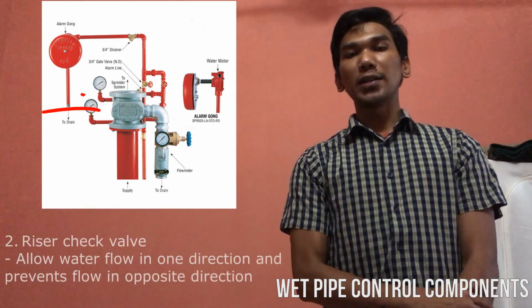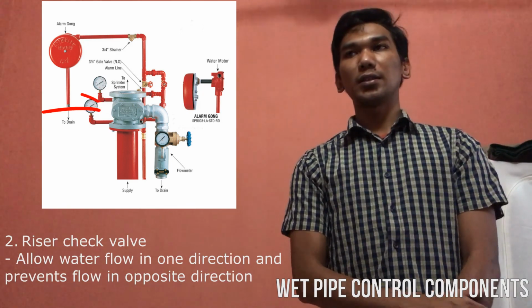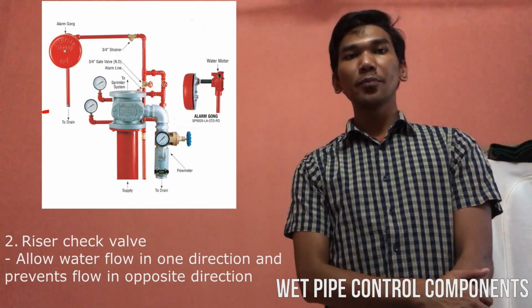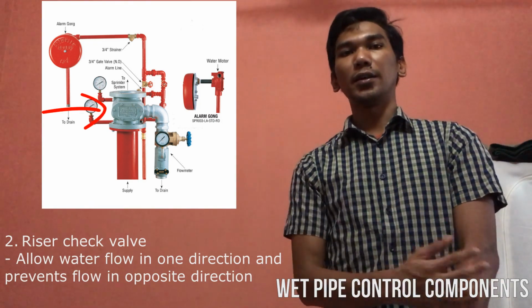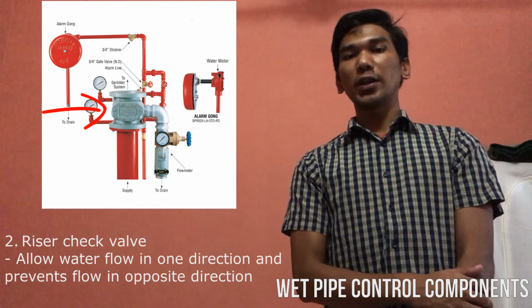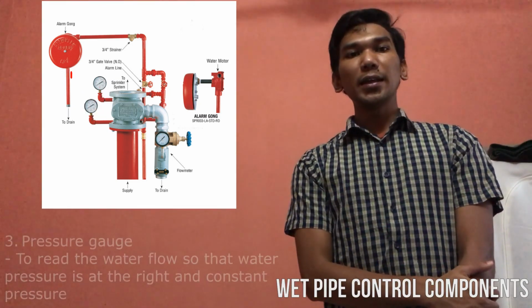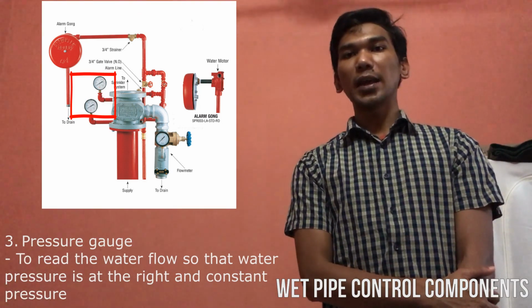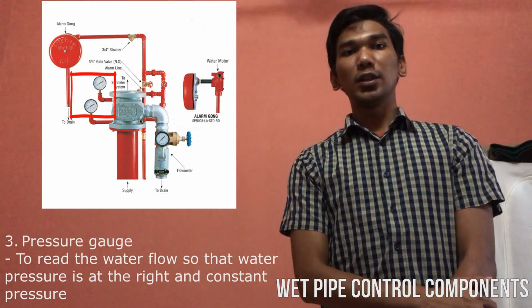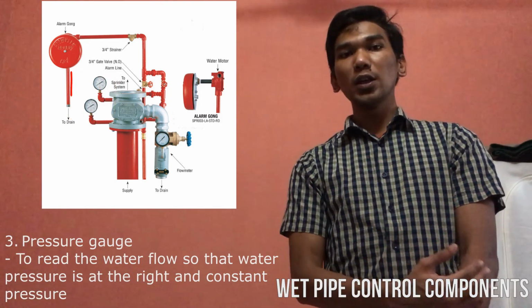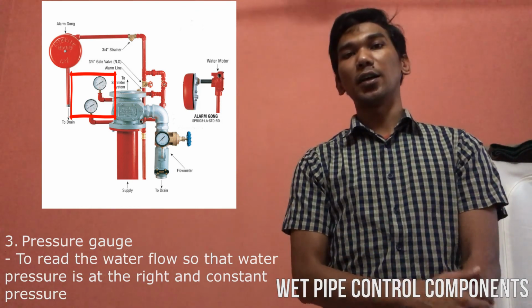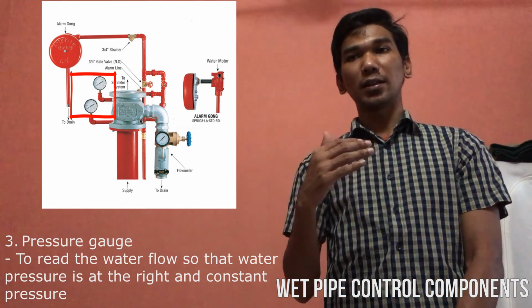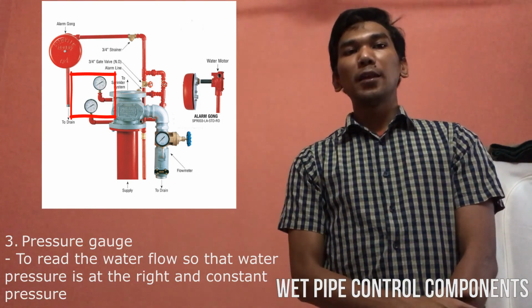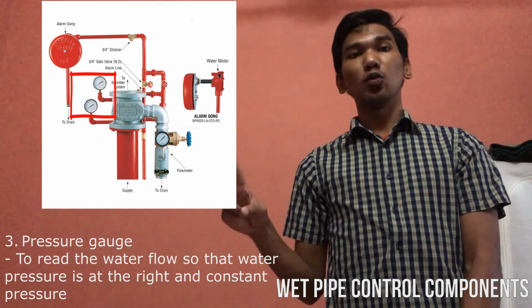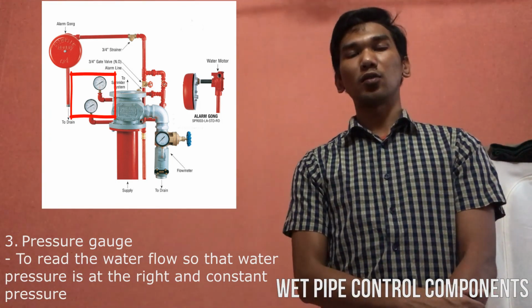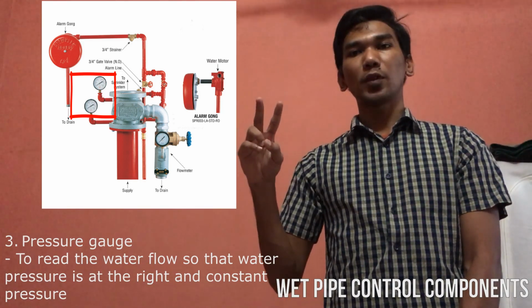And then the second one is the riser check valve. The riser check valve allows the water to flow in one direction only, and it prevents the flow in the opposite direction. This means that the water just goes in one direction only. And then the third one is the pressure gauge. Normally they have two pressure gauges. The function of the pressure gauge is to read the water flow so that the water pressure is at the right and constant pressure. So we can see that they must have two pressure gauges in order to read the water pressure evenly.